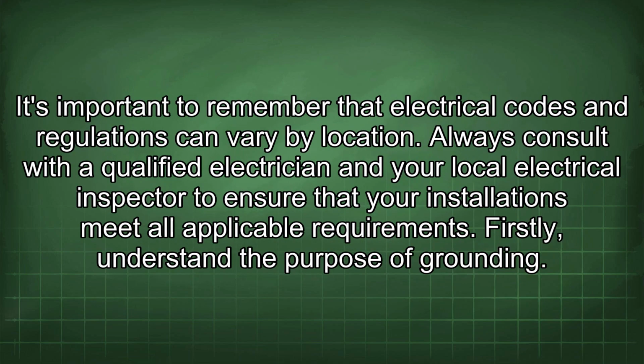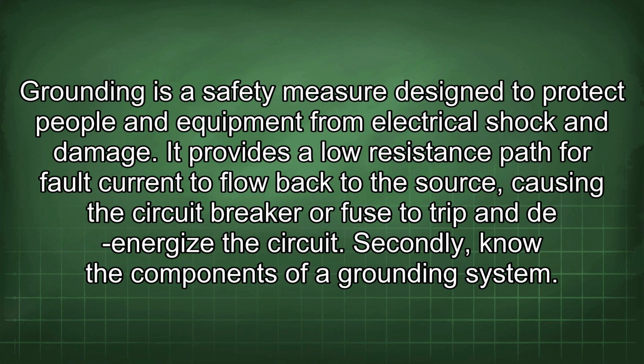It's important to remember that electrical codes and regulations can vary by location. Always consult with a qualified electrician and your local electrical inspector to ensure that your installations meet all applicable requirements. Firstly, understand the purpose of grounding. Grounding is a safety measure designed to protect people and equipment from electrical shock and damage. It provides a low resistance path for fault current to flow back to the source, causing the circuit breaker or fuse to trip and de-energize the circuit.